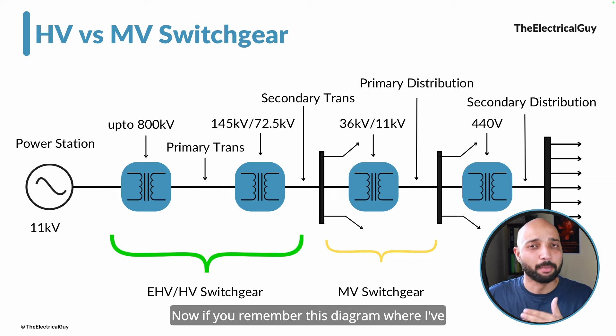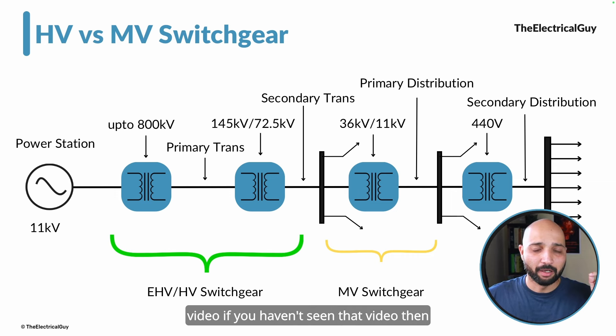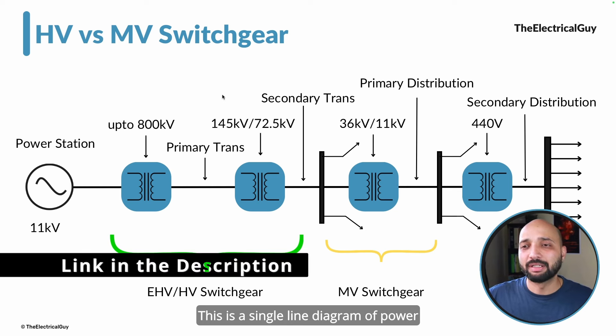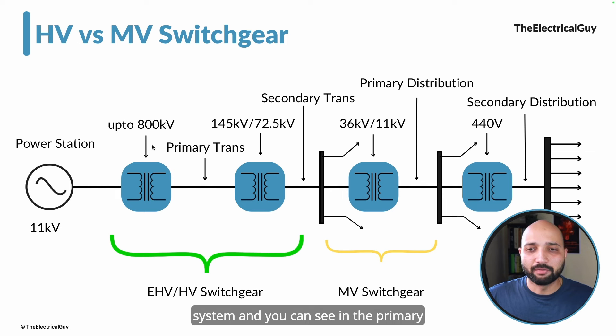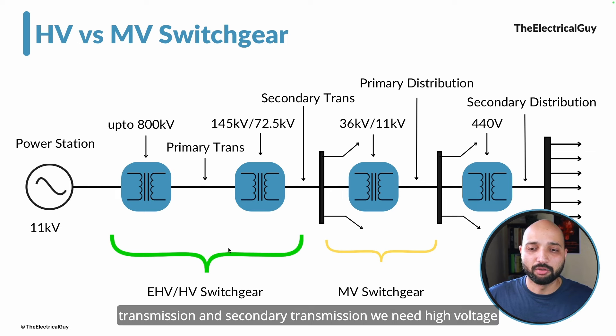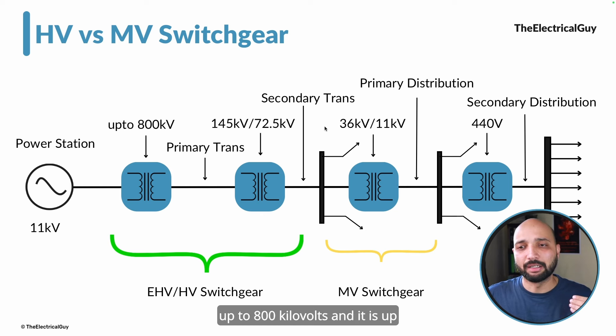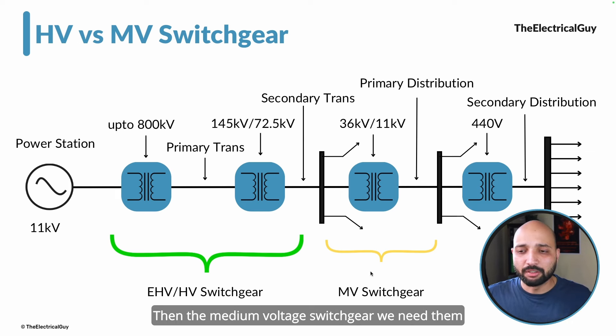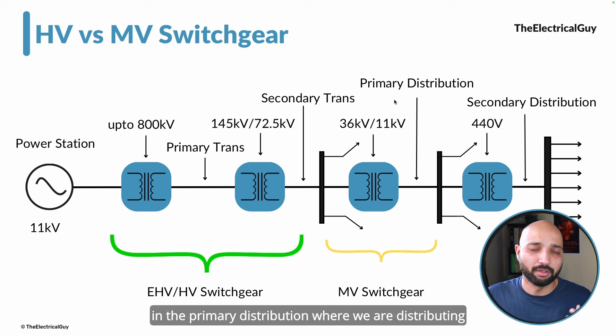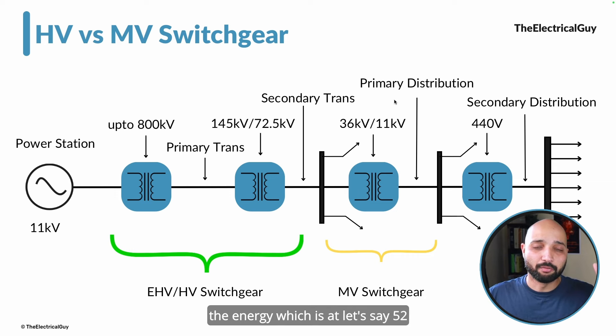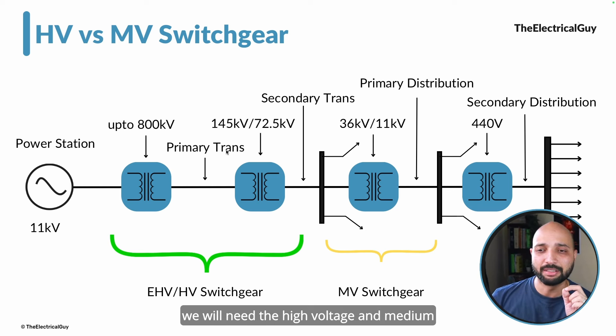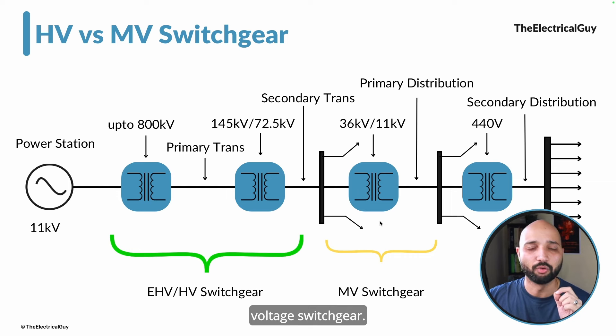In this single line diagram of the power system, you can see that in the primary transmission and secondary transmission we need high voltage and extra high voltage switchgear, which can go up to 800 kilovolts down to 72.5 kilovolts or 52 kilovolts. Then medium voltage switchgear is needed in primary distribution, covering roughly 52 kilovolts down to 1000 volts.